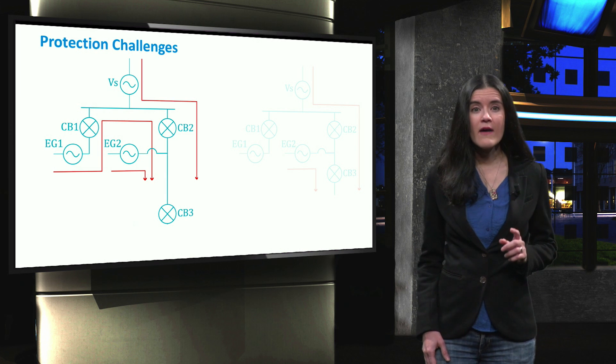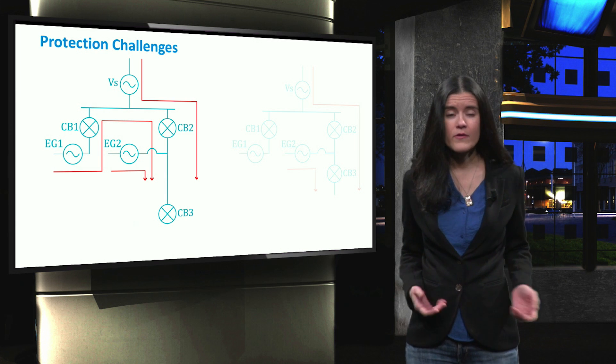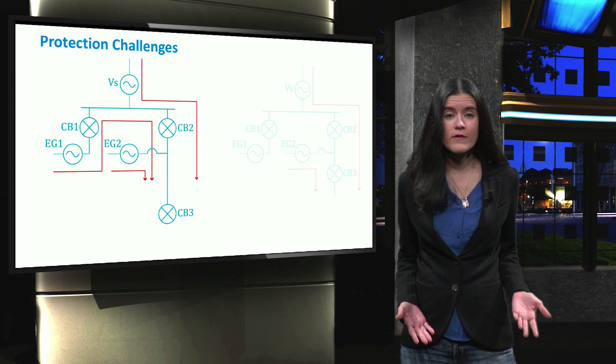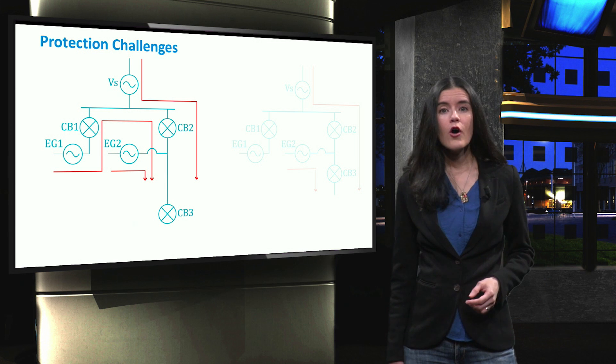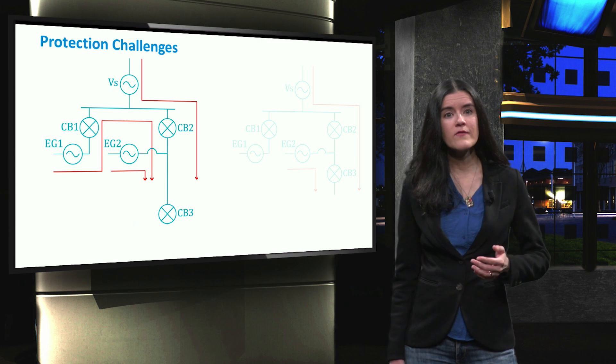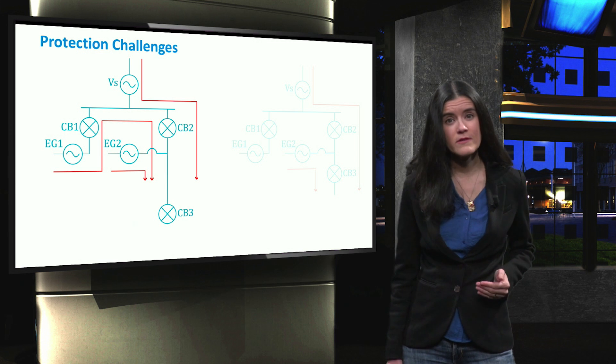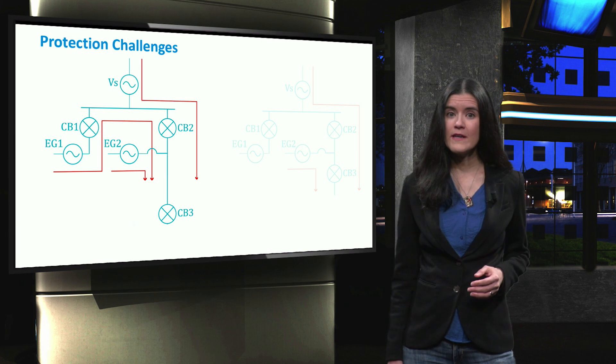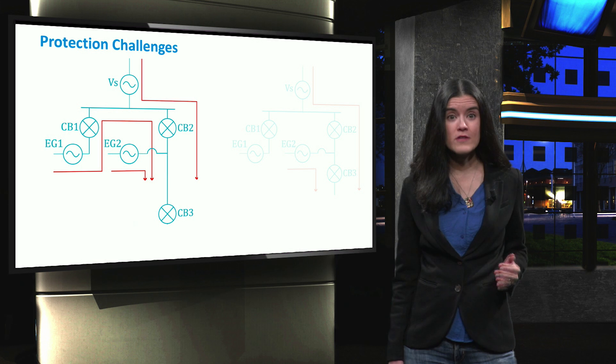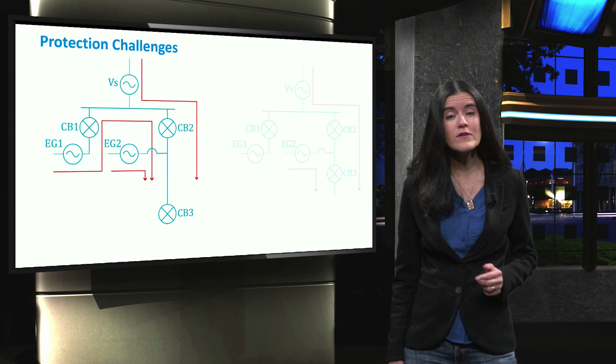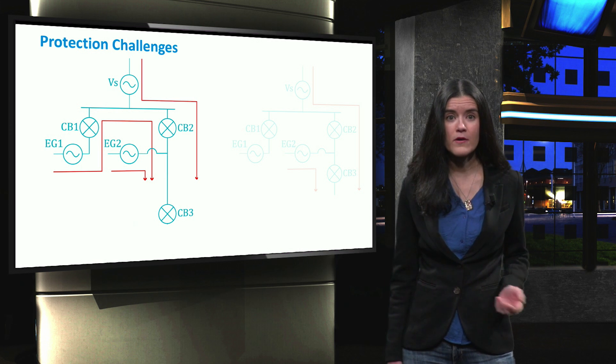As we have seen before, having distributed generators in a microgrid results in having bidirectional current flows. In the past, overcurrent protection was implemented for unidirectional flows exclusively. The lack of coordination among the overcurrent relays and circuit breakers can result in faulty or mal-operation in microgrids.